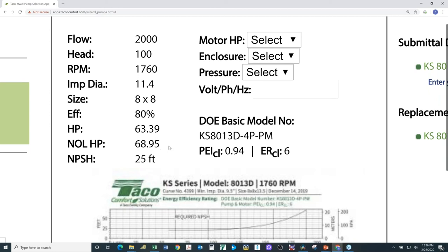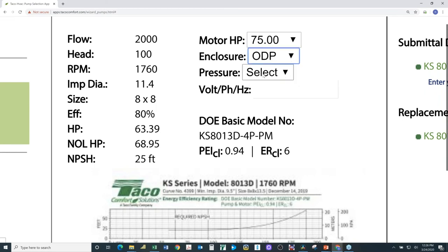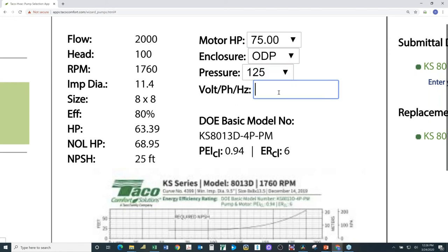I want to make a pump motor selection. I need a motor greater than 68.95 horsepower, because the non-overloading horsepower is the maximum amount of horsepower this pump can consume at 1760 RPM and 11.4-inch impeller diameter. So if I select a 75 horsepower motor, I know the motor will never overload for this pump-impeller combination. For the enclosure I'll pick ODP — open drip proof. The pressure I'll select is 125 pounds, and the voltage is 460 volt, three-phase, 60 Hz.